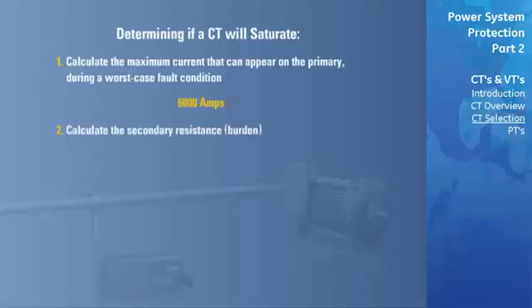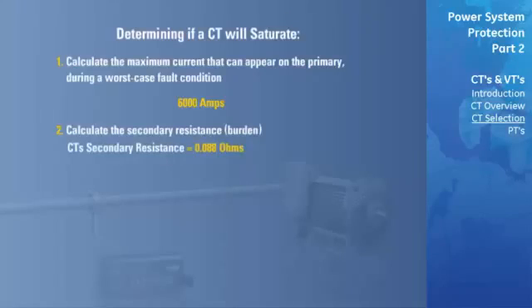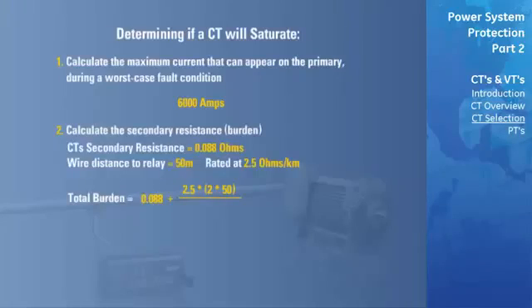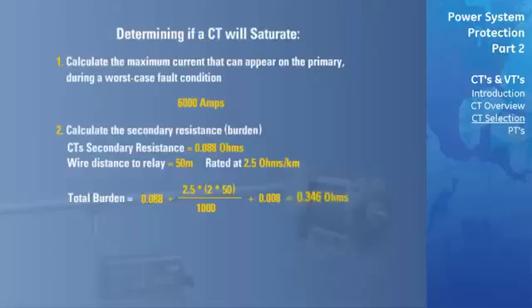Next, we will calculate the secondary resistance, or burden, using the stats provided. The phase CT's secondary resistance, that is the resistance of the windings on the CT, is equal to 0.088 ohms. The length of each wire from the CT to the relay is 50 meters and has a rated resistance of 2.5 ohms per kilometer. The total burden is equal to the CT secondary resistance of 0.088, plus 2 times the lead length of 50 meters multiplied by the lead resistance of 2.5 ohms per kilometer and then divided by 1,000 meters, added to the relay burden of 0.008 ohms, resulting in a total burden of 0.346 ohms.